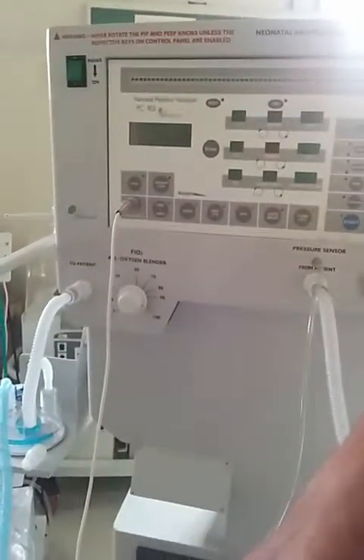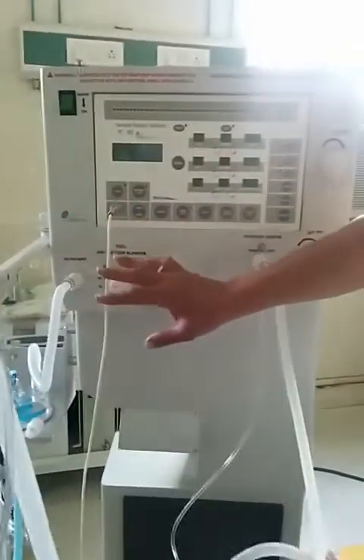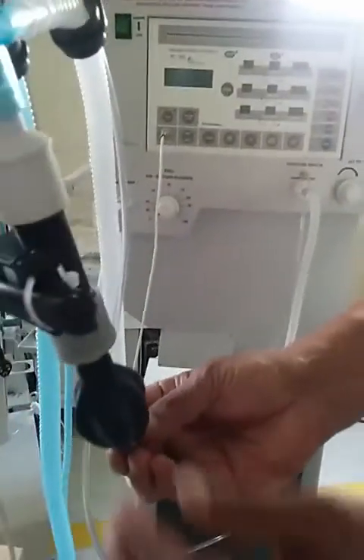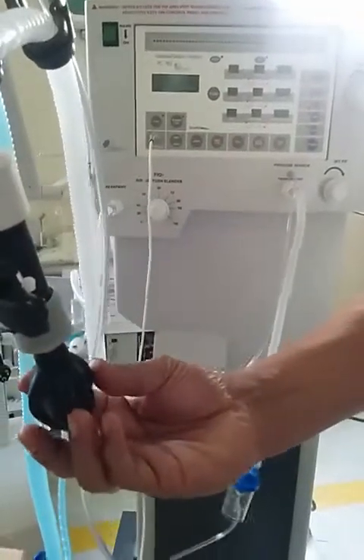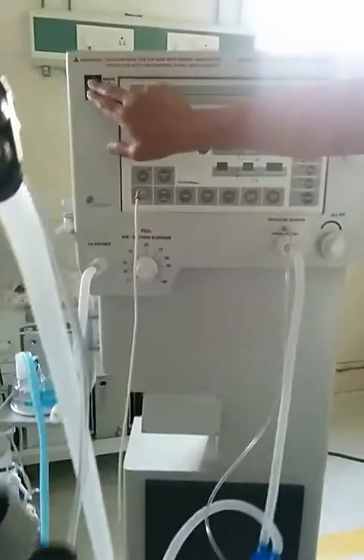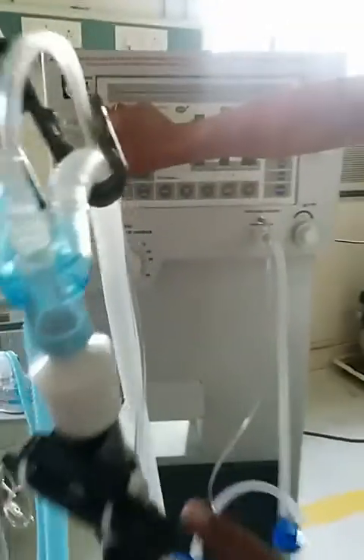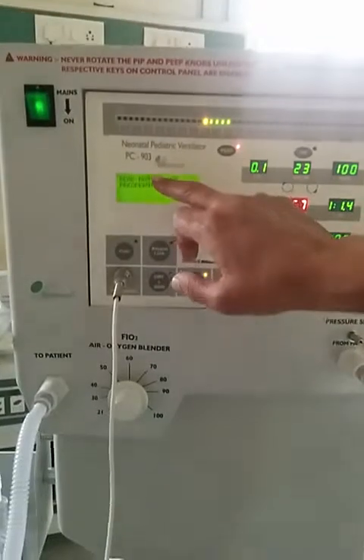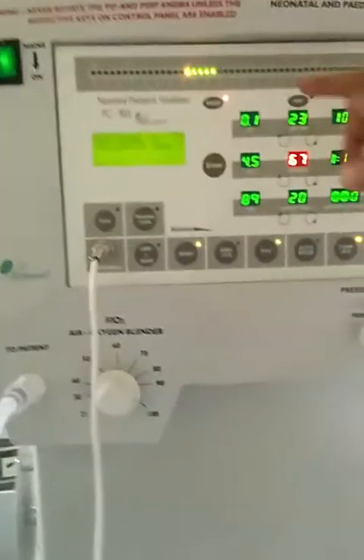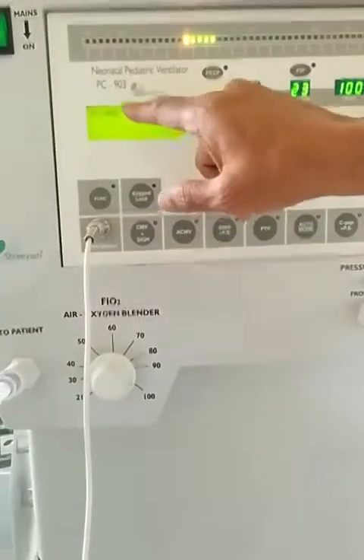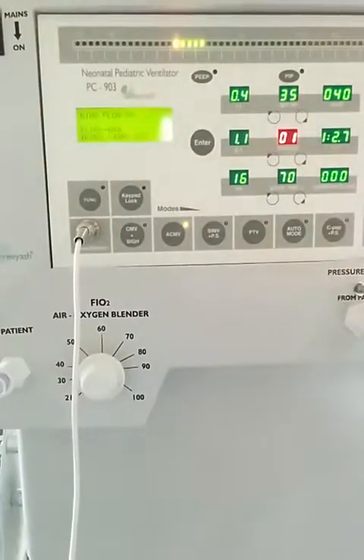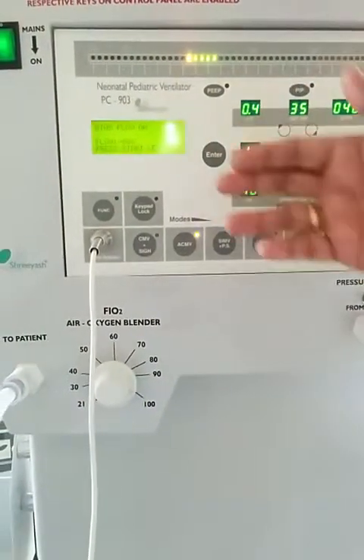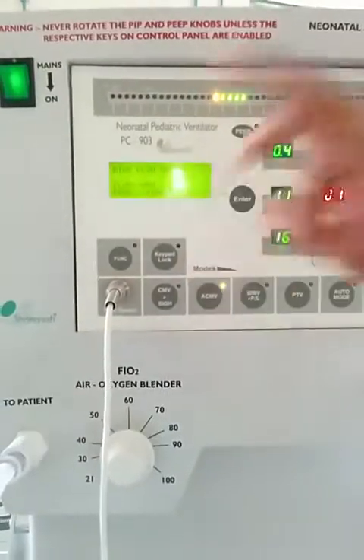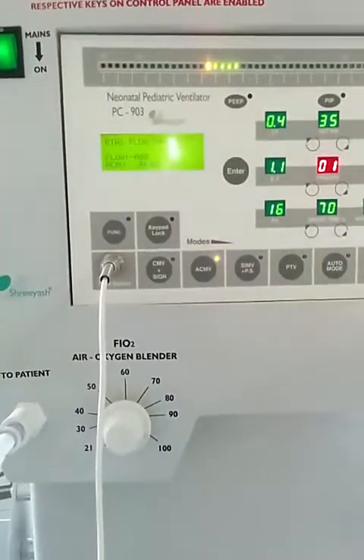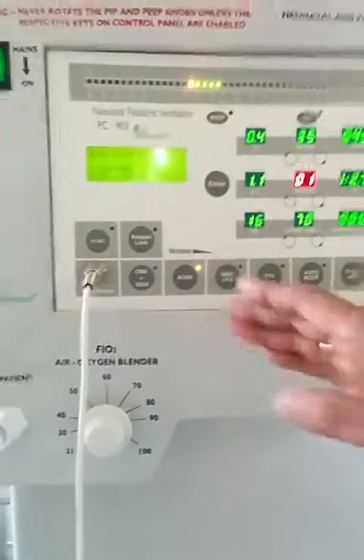Now, once all these connections are done, ensure that there are no leakages, and this test lung should be inflated. Once the test lung is inflated, put on the mains on switch of the ventilator. It will do a self-diagnostic check and will inform the user to read the instruction manual properly. After which it will show you the used hours of the machine and also show what the bias flow is. Now to set a certain mode, press any key that is desired.